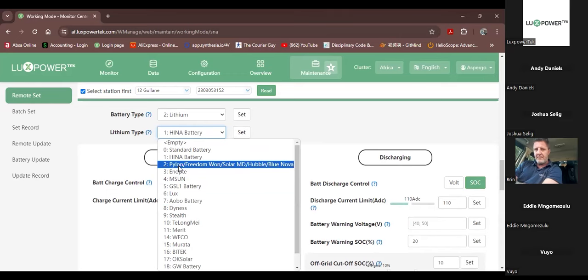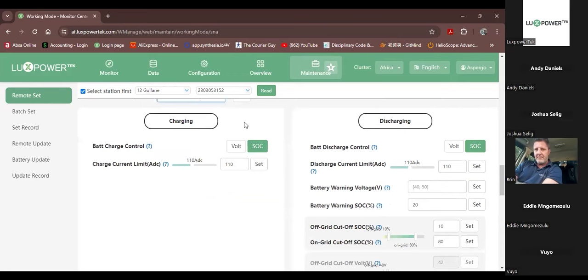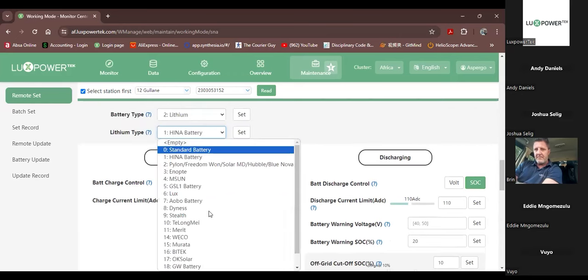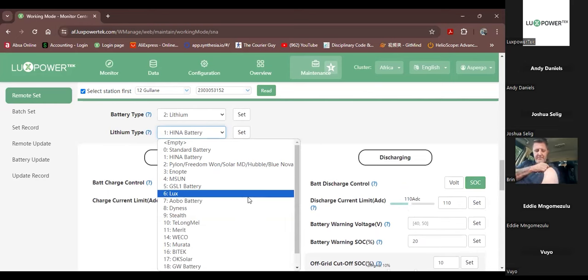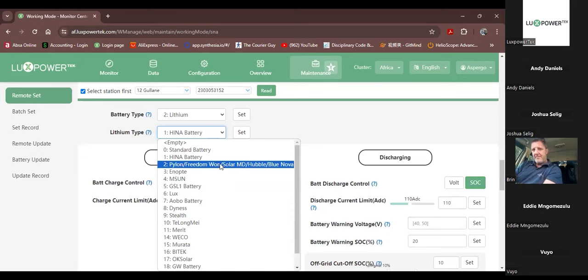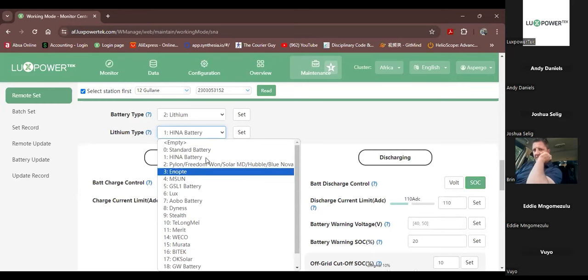So it's very important that if your battery doesn't appear on the list, even if the manufacturer tells you that you can use any one of these, it should work, then the onus or the responsibility of that falls on you, the installer, or the end user if they change the settings. But we will only back or warranty any of these here, because it means that these batteries have been tested in our lab and the protocol has been shared between manufacturer and manufacturer. So in other words, Lux Power and HINA shared, Pylon and HINA shared, Enopte, and so forth.